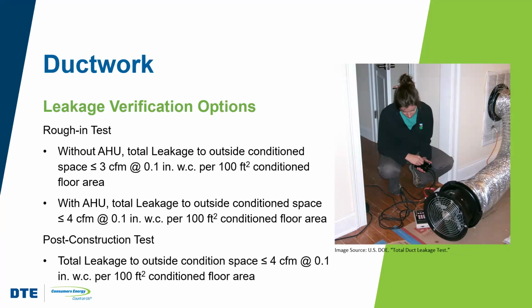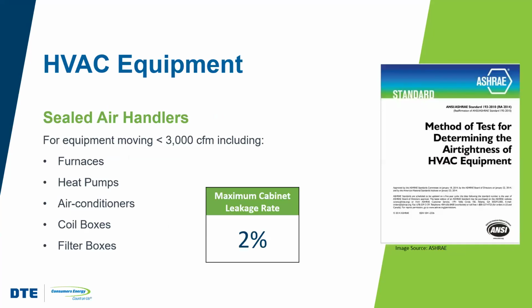Now, if the furnace is in place, the maximum allowed leakage rate is 4 CFM at 25 pascals or a tenth of an inch. If the furnace is not yet installed, the maximum allowed leakage rate is lower. It's 3 CFM, still at 25 pascals. Additionally, the furnace itself or the air handling device must have a manufacturer's listed cabinet air leakage rate no greater than 2% of its design airflow.